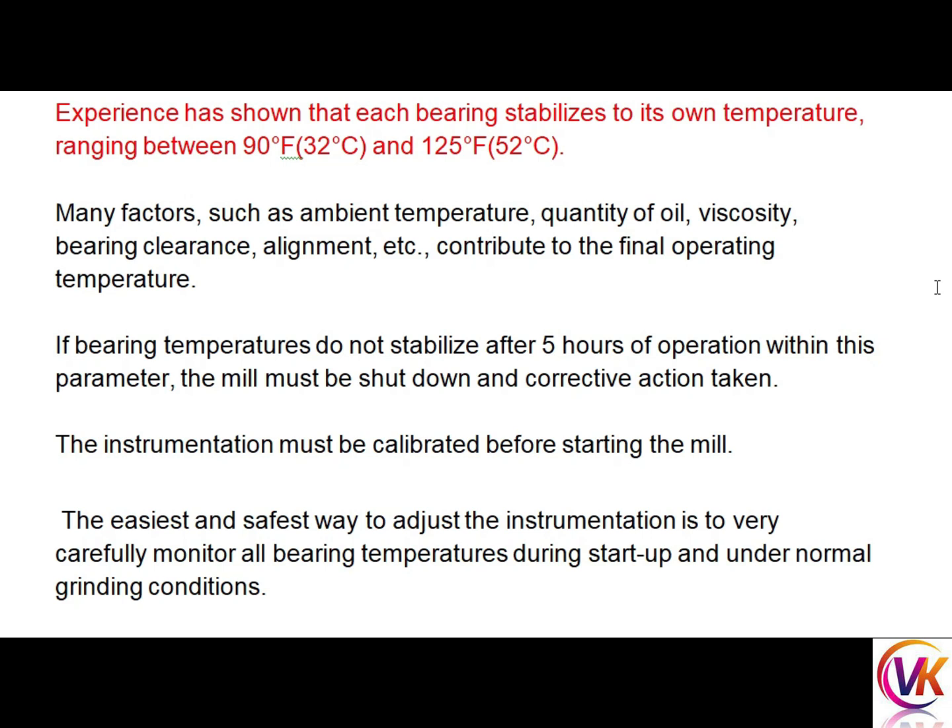Experience has shown that each bearing stabilizes to its own temperature, ranging between 32 degrees Celsius and 52 degrees Celsius. Many factors such as ambient temperature, quantity of oil, viscosity, bearing clearance, and alignment contribute to the final operating temperature. If bearing temperatures do not stabilize after five hours of operation within these parameters, the mill must be shut down and corrective action taken.